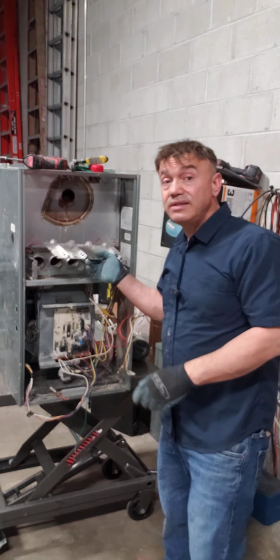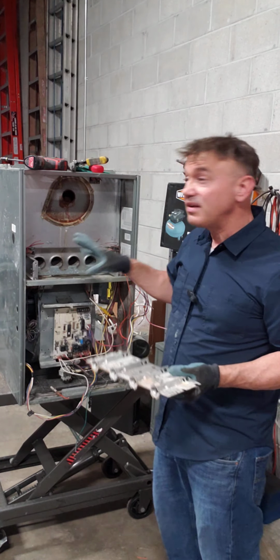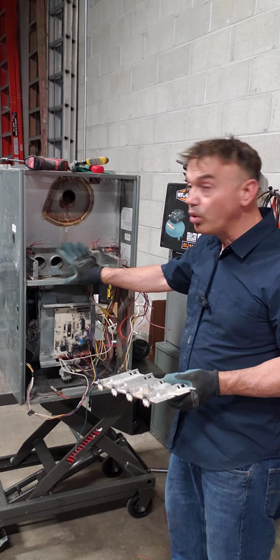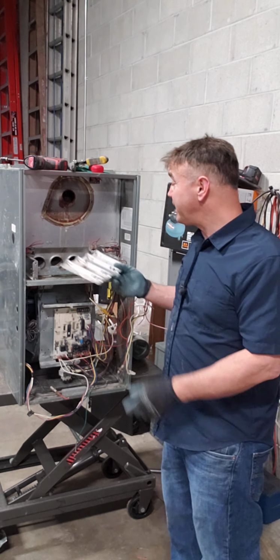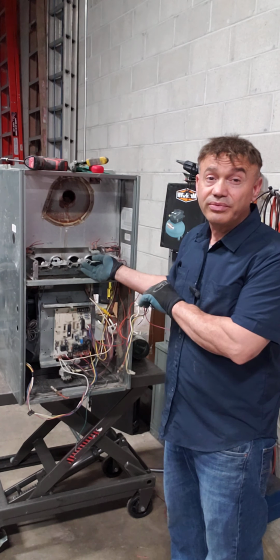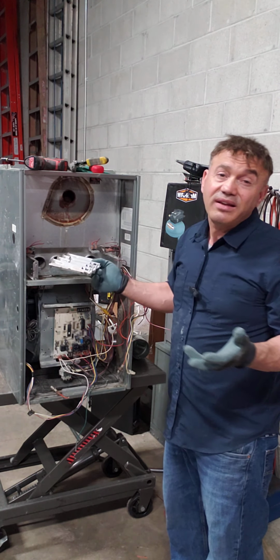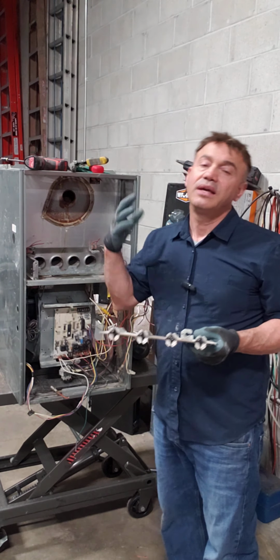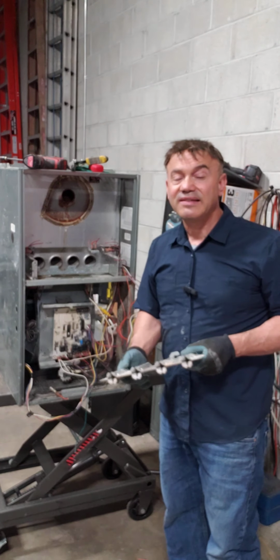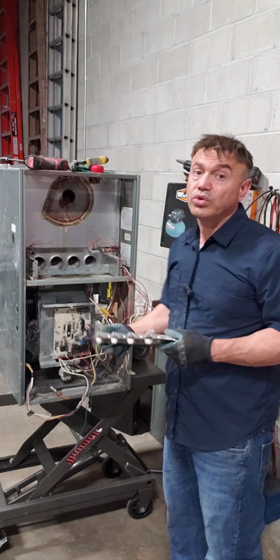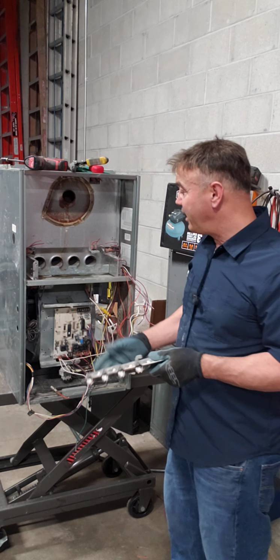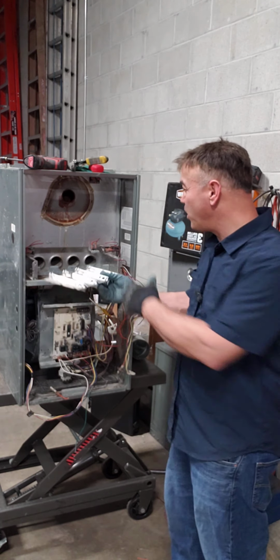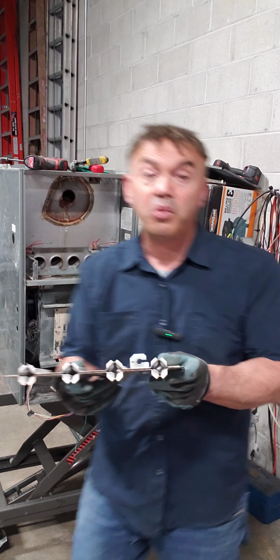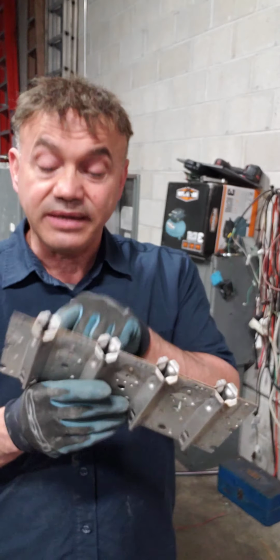But sometimes we don't see the burner. Some furnaces have like a box. They're closed, and when we get a signal of a bad flame sensor, we think it's a bad flame sensor. We take it, we clean it. It's the same thing. We get a new flame sensor. It's the same thing. We get a new control board. It's the same thing. No matter what we do, and then finally we open the box. Oh, wait a second! Wow, this one is not igniting.